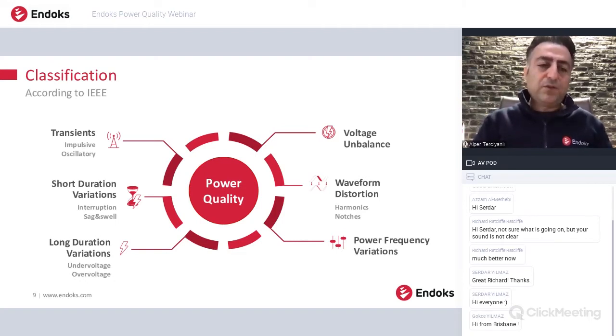And then the long duration under voltage and over voltage. Under voltage and over voltage mean, for example, the 10 minute average value of the voltage. Under the definitions, for example EN 50160, we say 0.9 per unit up to 1.1 per unit. So there is a band there. If the voltage magnitude is out of this band, then we call it over voltage or under voltage.